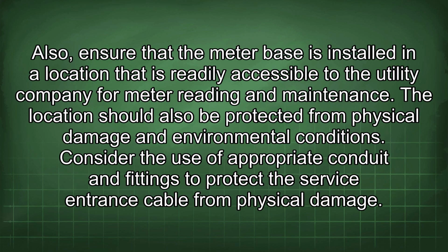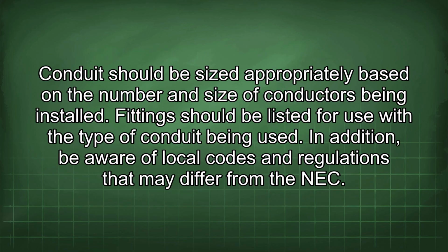Also, ensure that the meter base is installed in a location that is readily accessible to the utility company for meter reading and maintenance. The location should also be protected from physical damage and environmental conditions. Consider the use of appropriate conduit and fittings to protect the service entrance cable from physical damage. Conduit should be sized appropriately based on the number and size of conductors being installed. Fittings should be listed for use with the type of conduit being used.